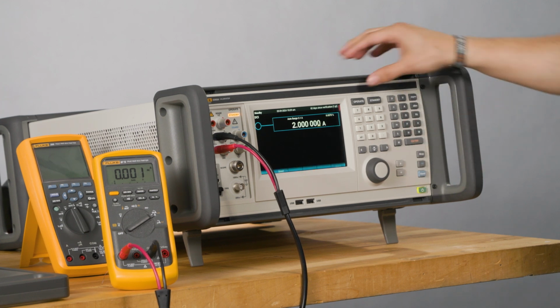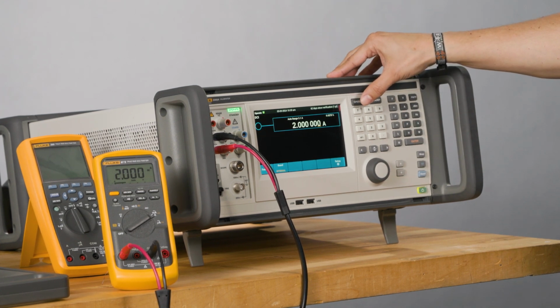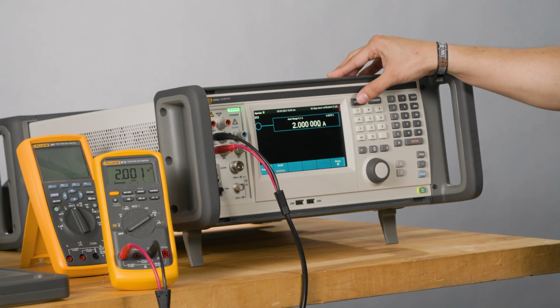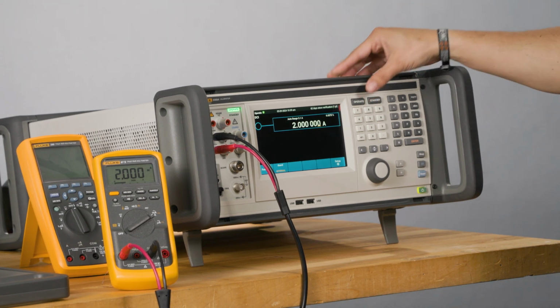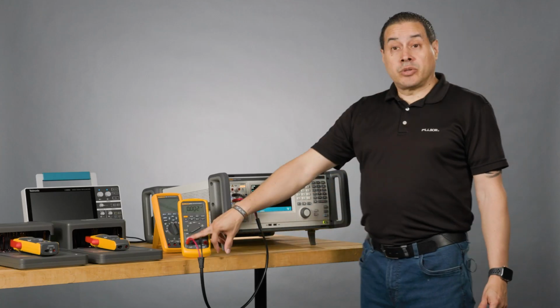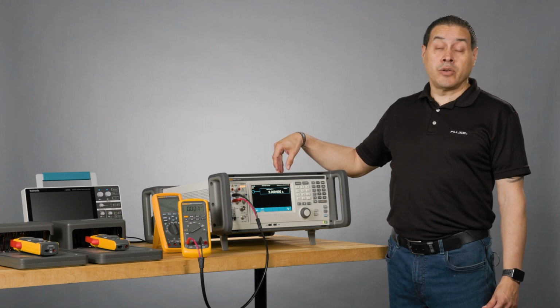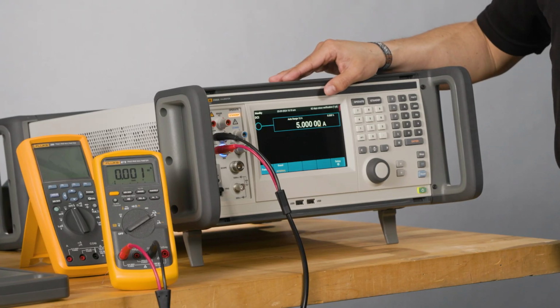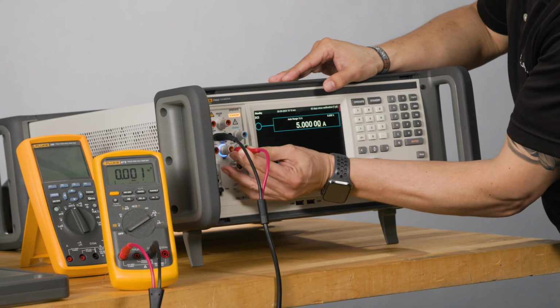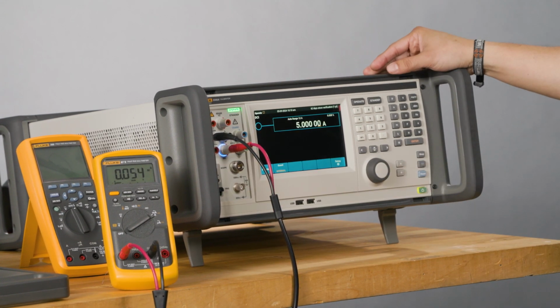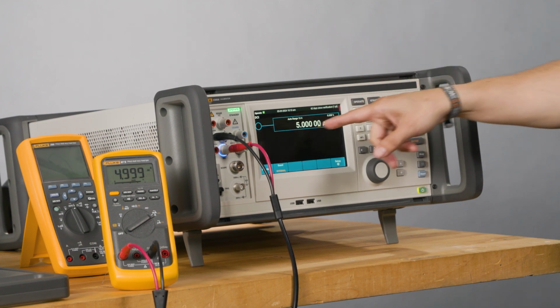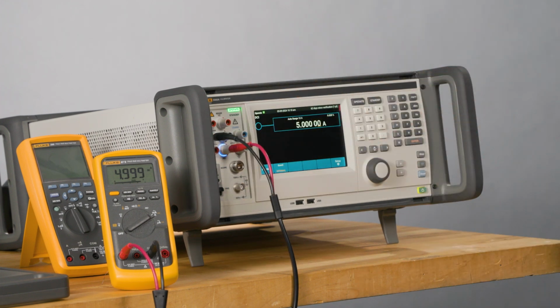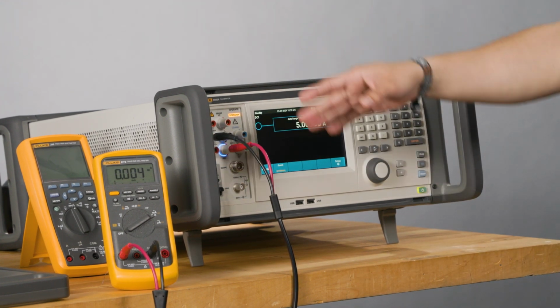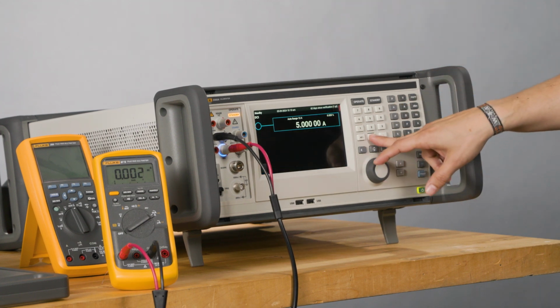2 amps. 2. Spot on. This meter goes up to 10 amps. Be careful because this unit goes to 30 amps. Don't break it. If you exceed the current, you're going to break the fuse. For 5 amps, I need to change the post here in my calibrator. Then I sent 5 amps and I'm getting 4.999, which is common and good. I'll be doing more points, up to 10 amps, which is the last one.